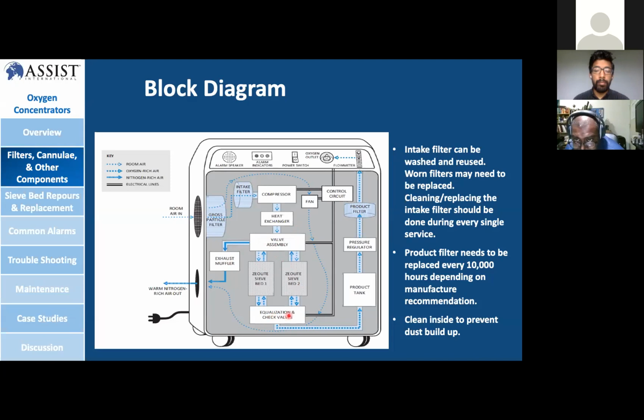So the equalizer and the valve go to the product tank, making sure that particular flow is stable on the product tank, and you go through the pressure regulator and the product filter and to the output with the flow meter. So remember, the product filter needs to be replaced every 10,000 hours. And remember that every single oxygen concentrator that you're going to see has an hour meter that will indicate how many hours you've been using that particular oxygen concentrator.